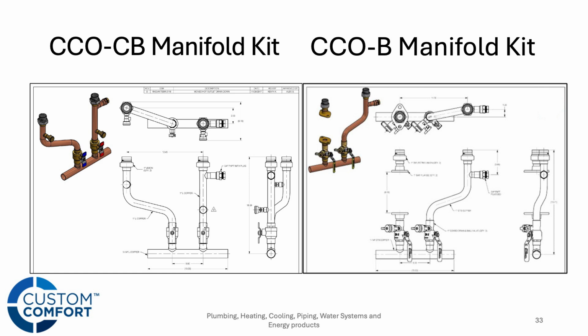The heat only manifold has flanges to accept a pump, right? The heat only boiler does not have a system pump built in internally. You would install that on the manifold kit there. The combi boiler is going to have that built in. So we just have the 2 pipes coming down, hot and cold going out for closely spaced tees there. Super important, of any of the issues that we've seen in some of the startups on these: if you don't have some type of hydraulic separation, you're going to have a problem. That pump's going to air out with an error code and it's going to cause you problems. So hydraulic separation, super important on both of these. Hammering that point home because we're going to have a different story when we talk about the fire tube later here.